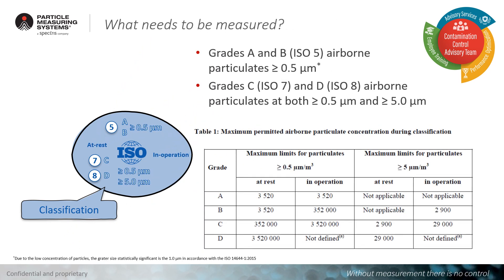Another significant change, which is in reality in alignment with the ISO, is that due to the low concentration of microparticles in low contamination areas such as grades A and B, we should measure only particles with an average size greater than 0.5 micron. The Annex 1 also asks that we evaluate the measurement of particles greater than 1 micron, but we will go in-depth on the reason for that in another dedicated webinar. Note that nothing has changed for grades C and D.